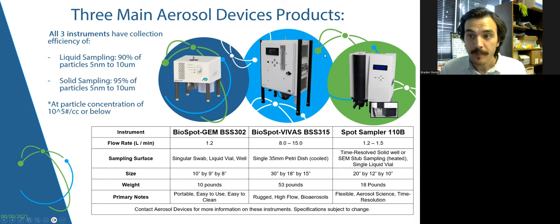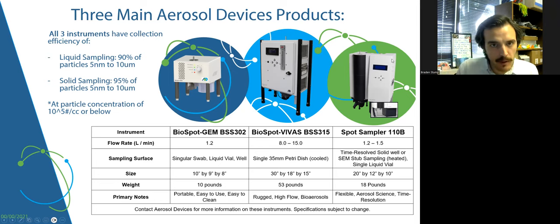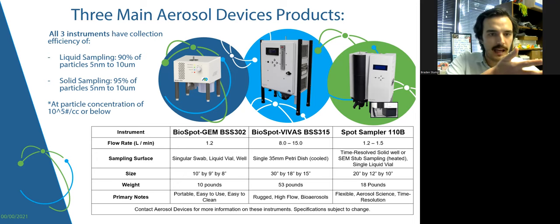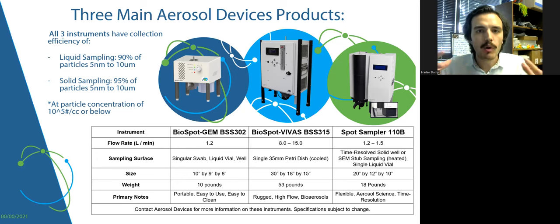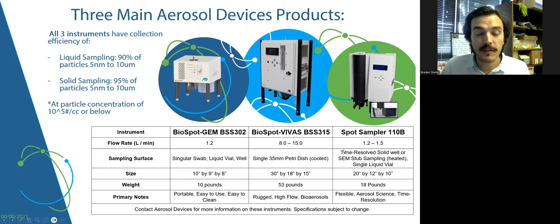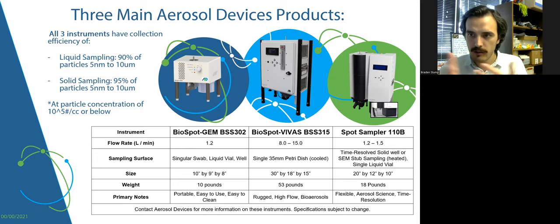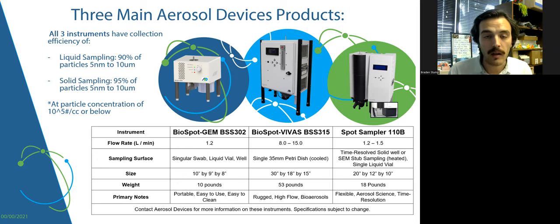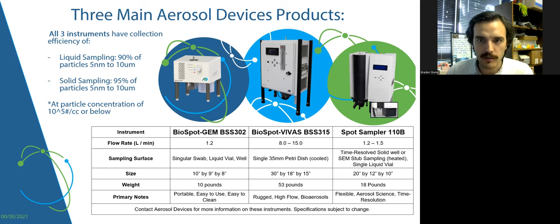Moving from the BioSpot GEM to the SPOT Sampler 110B: the SPOT Sampler is a little less aimed at industrial health and indoor air quality compared to the BioSpot GEM. It is the most flexible instrument and also our oldest instrumentation line — slightly larger, 18 pounds compared to the 10 pounds of the GEM, about double the volume. It has been utilized in aerosol chemistry, aerosol science, and bioaerosol runs. Its specific niche is time resolution in sampling: there's a time-resolved solid well or a time-resolved scanning electron microscope stub tray that can rotate between positions to sample into, but it will also sample into singular liquid vials. Its flow rate is 1.2 to 1.5 liters per minute, and it is the most flexible for different experimental needs of the three classes of instrument.